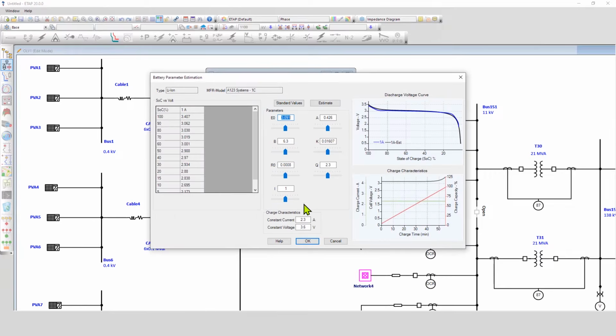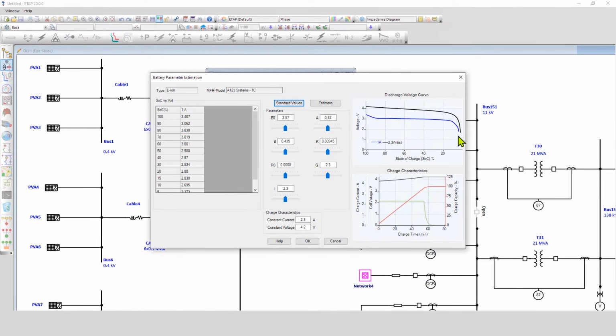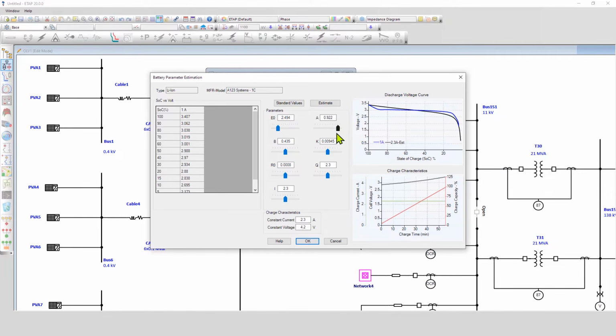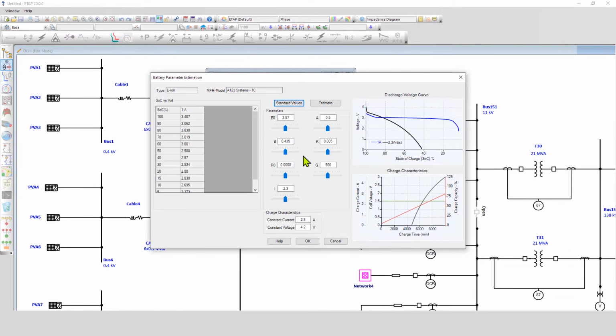Looking at the parameters for the lithium-ion battery, the program allows you to essentially define standard values that recomputes the standard curve versus the previously estimated curve. You can then also change the exponential portion of the charge and discharge characteristics, and in near real time observe the change in these variables as it affects the charge and discharge characteristics and the profile of the battery. Once you're happy with the profile that you have created, you can then go ahead and start utilizing this particular battery that has estimated parameters along with various simulations within ETAP.